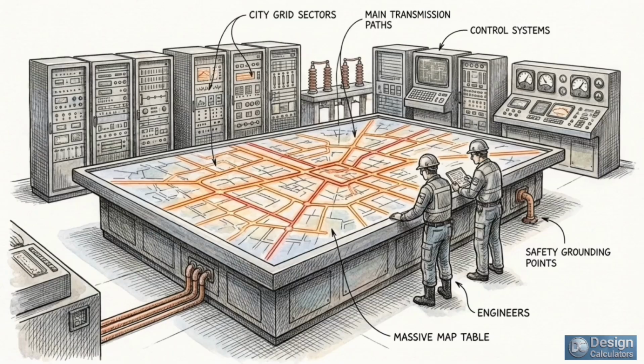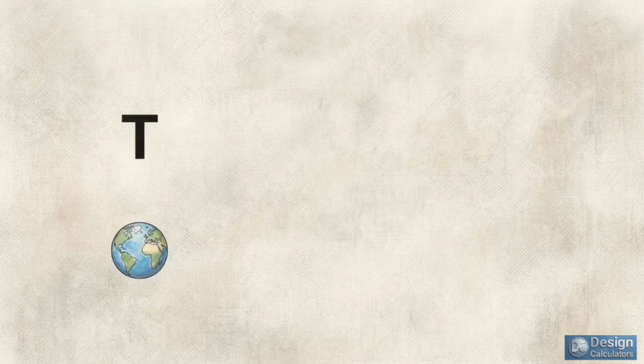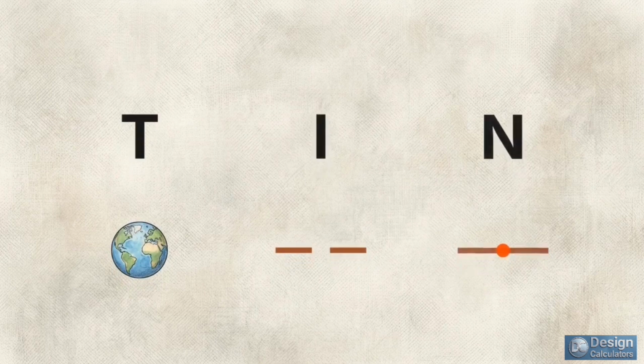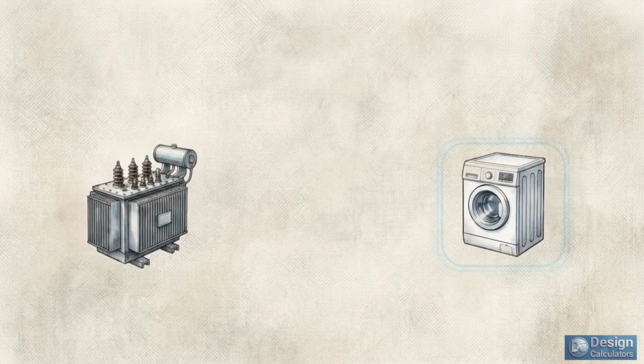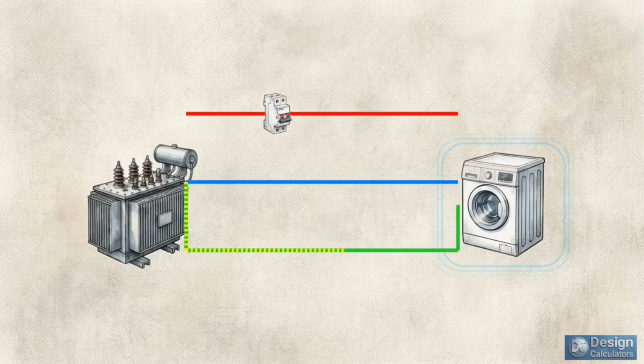Engineers classify different grid architectures using a global code based on a simple alphabet. T stands for terre, the French word for earth. I means isolated, and N stands for neutral. This diagram illustrates the most common industrial and residential setup, the TN or terre-neutral system. Notice how the metal casing of the appliance is tied directly back to the transformer's neutral point using a dedicated protective earth, or PE, wire.